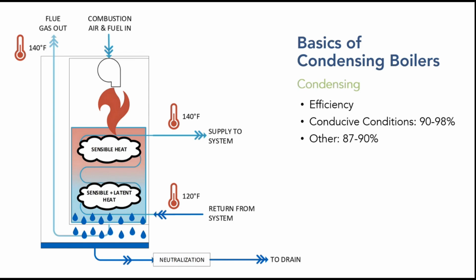In condensing mode, what I'm calling conducive conditions, you can get a 90 to 98% efficiency. Otherwise, 87 to 90% efficiency is basically an advanced conventional boiler. If you're not in condensing mode, you're basically turning your condensing boiler into a conventional boiler and not getting that extra efficiency. And we'll talk more about that.